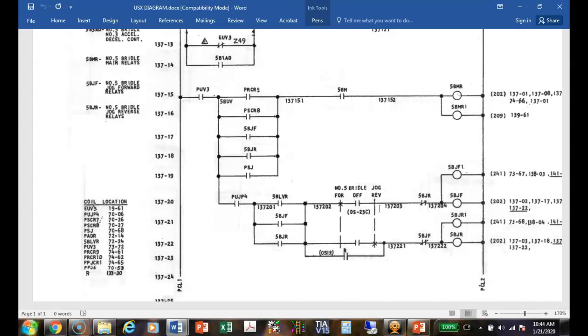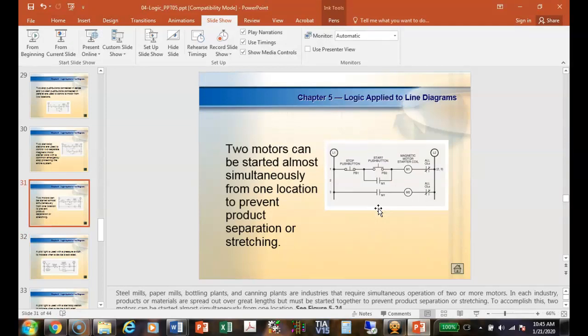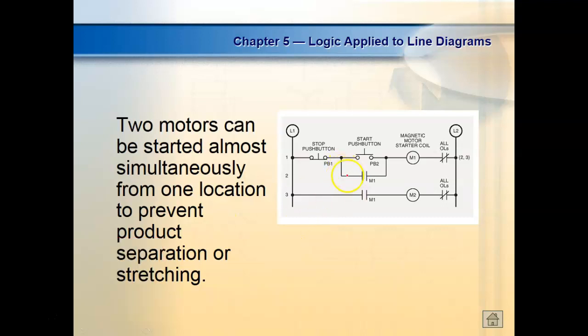It's just momentary — what we call it. If I came back into this circuit and added a normally open switch — just easier to understand — if I opened that switch, the thing wouldn't re-latch, it wouldn't seal in, so now we've turned this into a jogger.